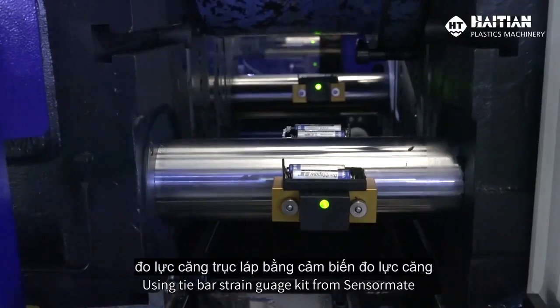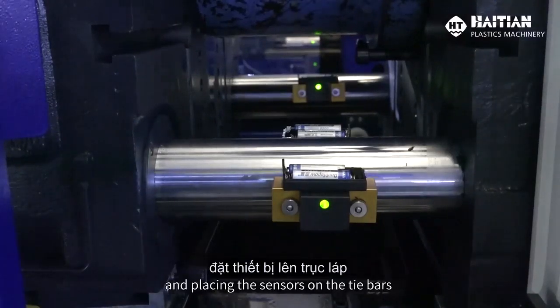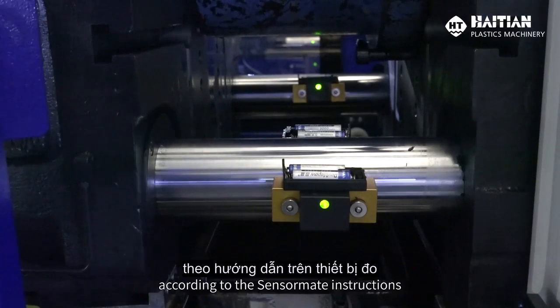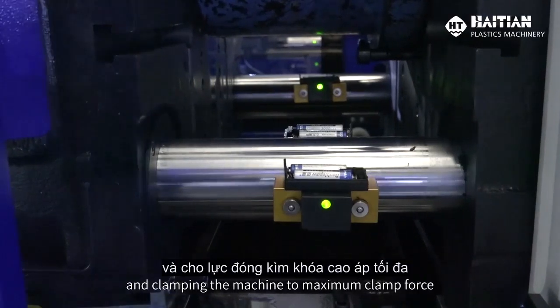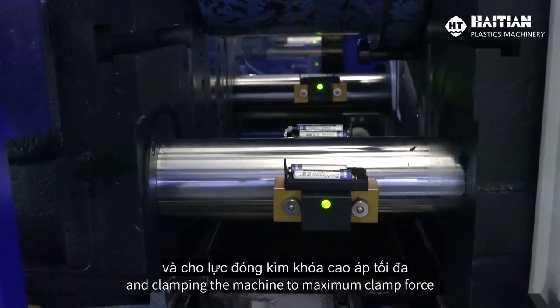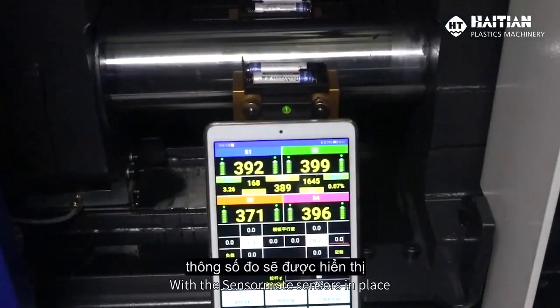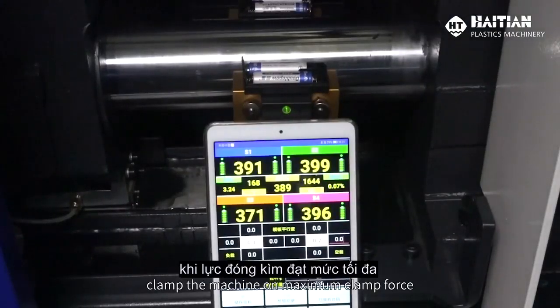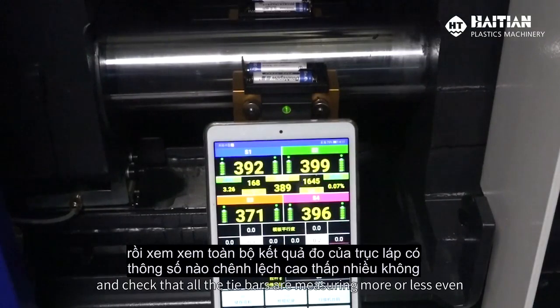Using a tie bar strain gauge kit from Sensormate and placing the sensors on the tie bars according to the Sensormate instructions and clamping the machine to maximum clamp force. With the Sensormate sensors in place, clamp the machine on maximum clamp force and check that all the tie bars are measuring more or less even.